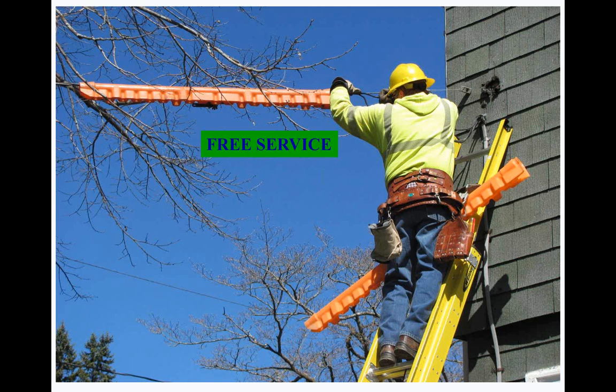So if you're going to do that yourself, you can typically call the utility and say, I need my power shut off from like 8 to 4 on Saturday morning, I got a tree person coming on and trim all of that stuff away. Because if you get a tree rubbing against some of these wires, they can wear that out. They can cause those issues of the flickering lights, the bad neutral, the things you don't want to happen.